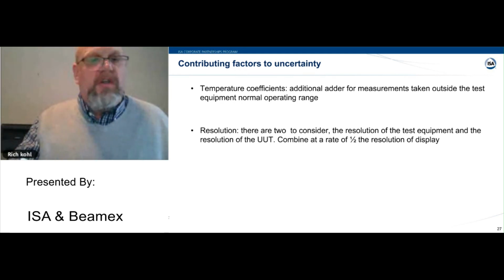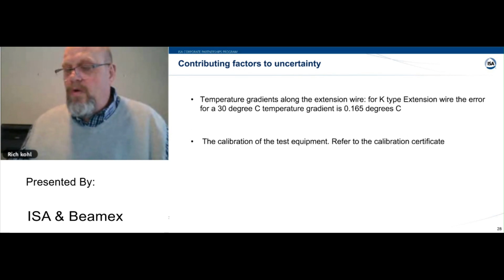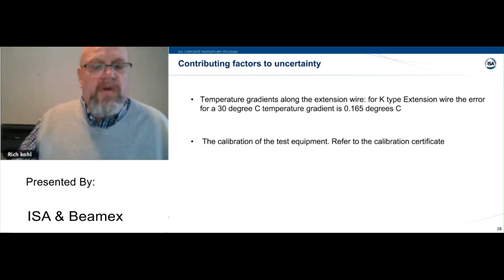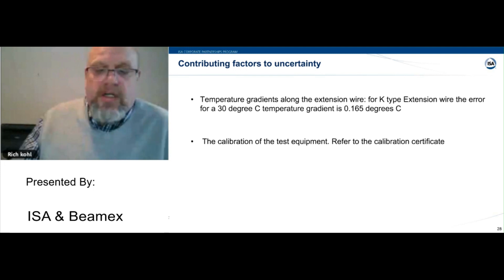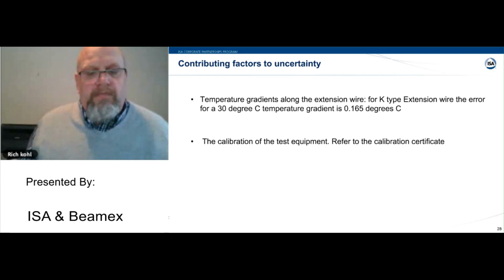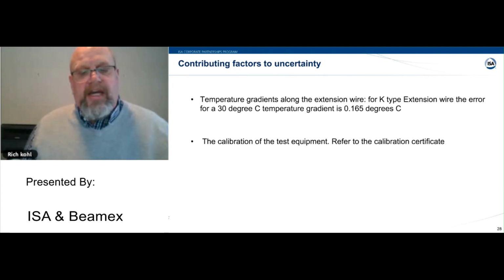So, okay, let's move on to the next items here. Now, the temperature gradients along the extension wire: for a K-type extension wire, the error for a 30-degree temperature gradient across the length of that whole extension wire that you're using is 0.165 degrees C.